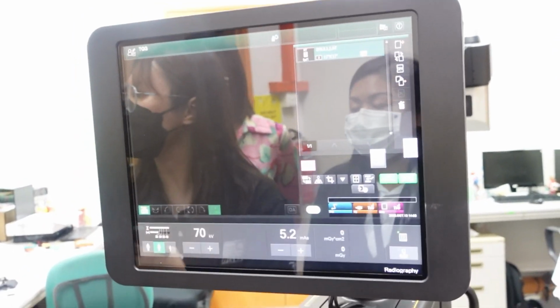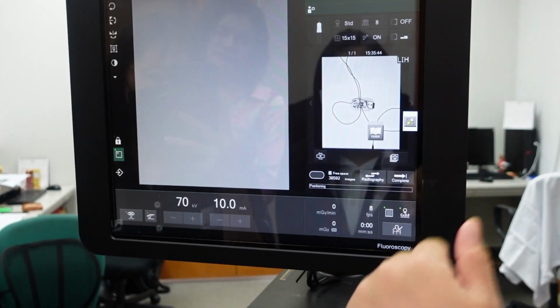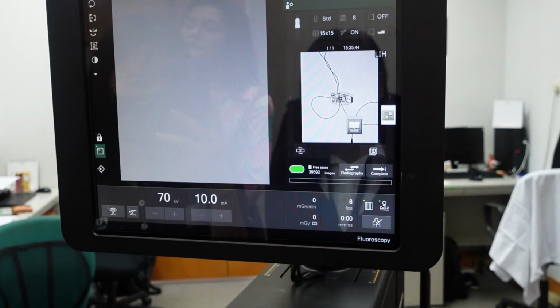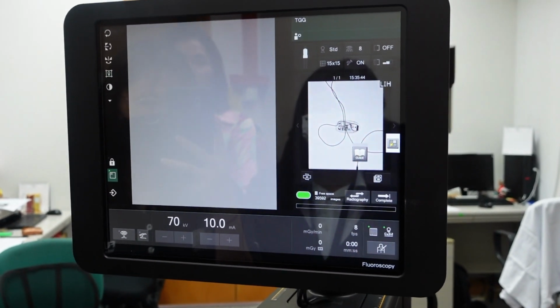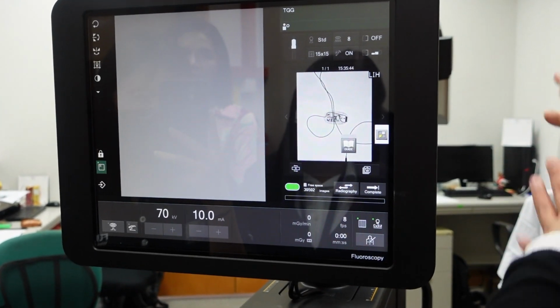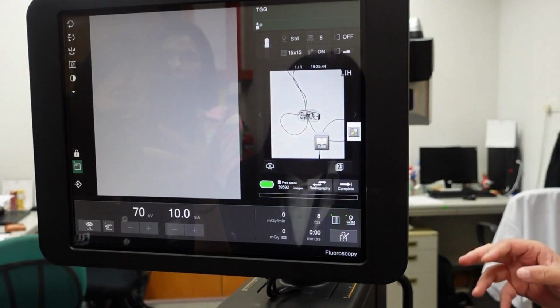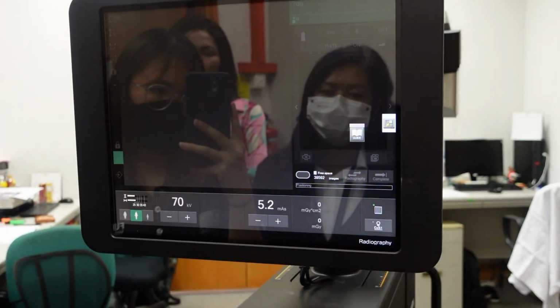Just to add to the point she said, kV, right? Always do 70 kV 10 mA, however many times you have to do it. It is mentioned in the warm-up. This is to avoid tube arcing. So this one is done. Now let's go to the console advanced.